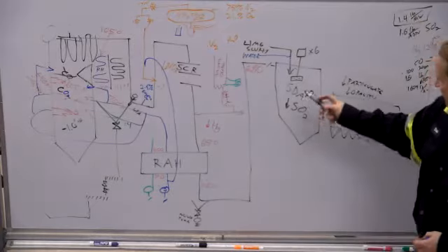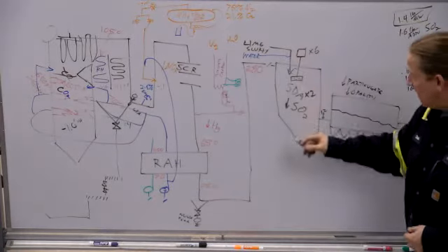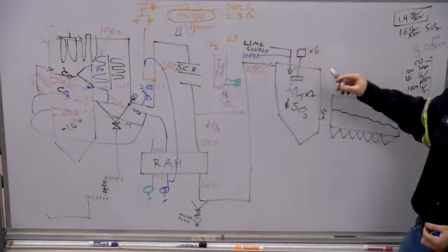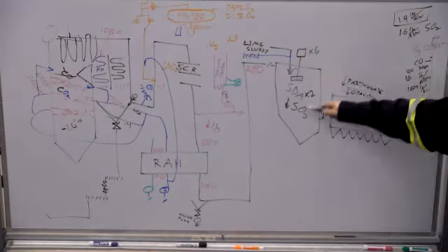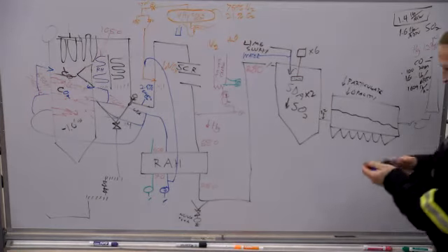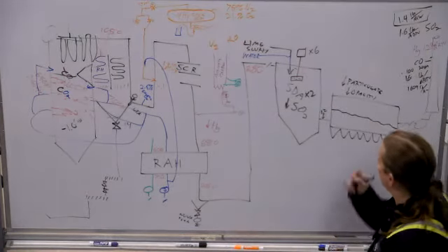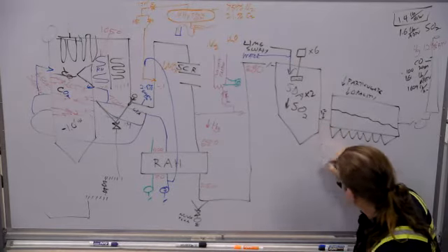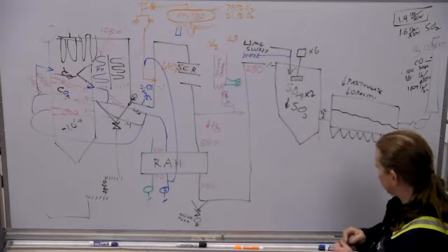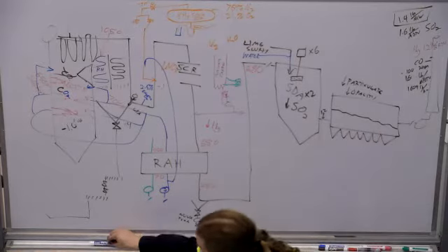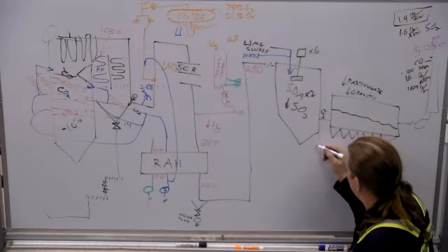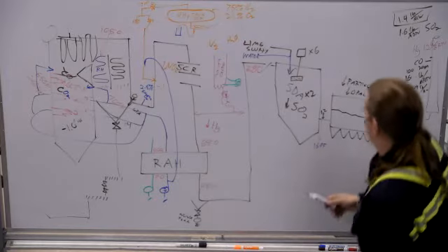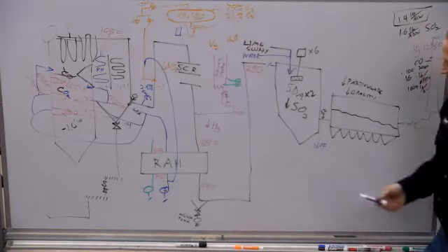All right. So you're spraying lime slurry, which is, you know, 80% water, and you're spraying water, and then that mixes with flue gas and cools it down. And so coming out, you're looking at 169. Wow, I guess purple is the new red. About 169 Fahrenheit on the outlet.